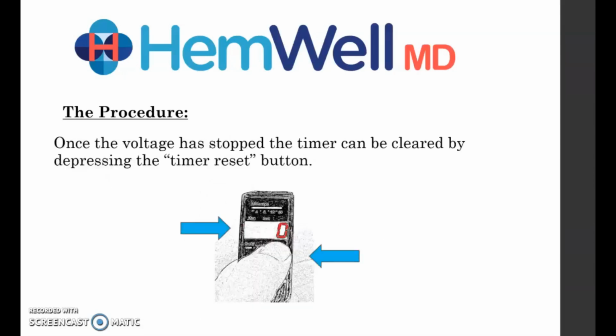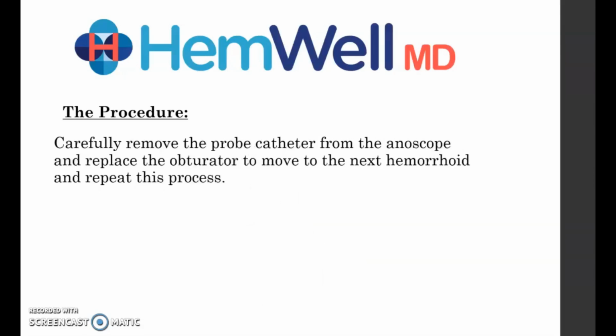Once the voltage has stopped, the timer can be cleared by depressing the timer reset button. Record treatment time on the chart. The timer reset is not dependent upon the probe catheter touching the patient and can be performed anytime. Carefully remove the probe catheter from the inside of the anoscope and set the control handle aside. Clean off any fecal material or excess lubricant from the tip of the probe catheter with a 4x4. Insert the obturator back into the anoscope and make the decision of ending the treatment or moving on to the next hemorrhoid.